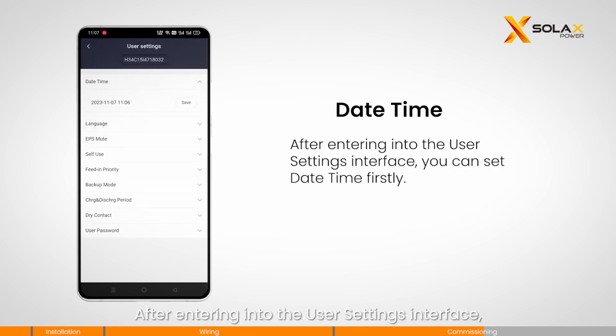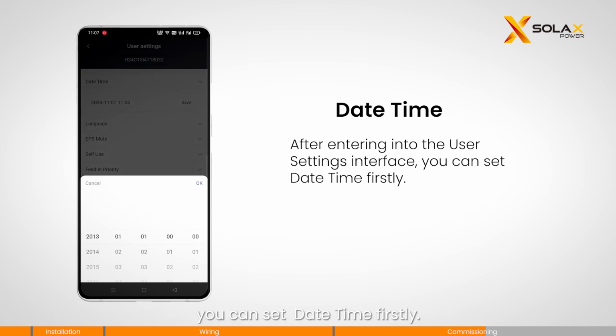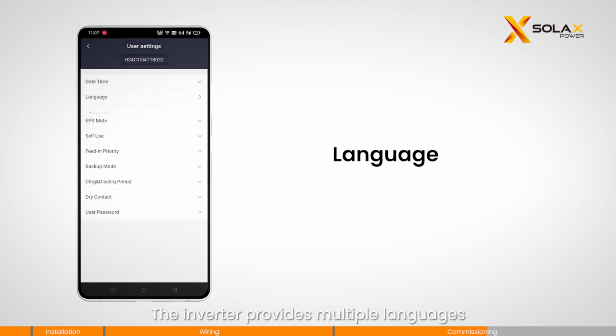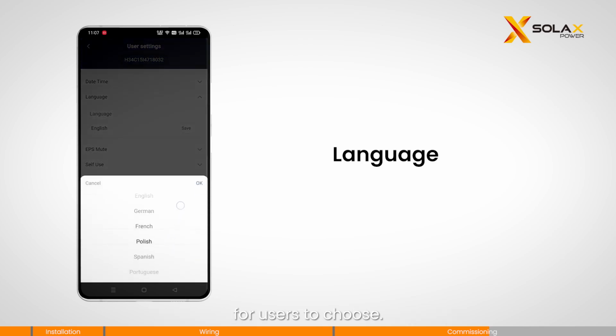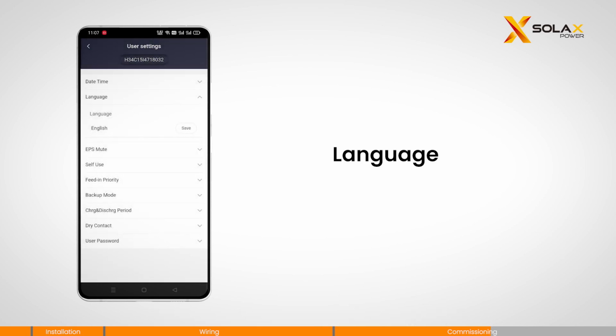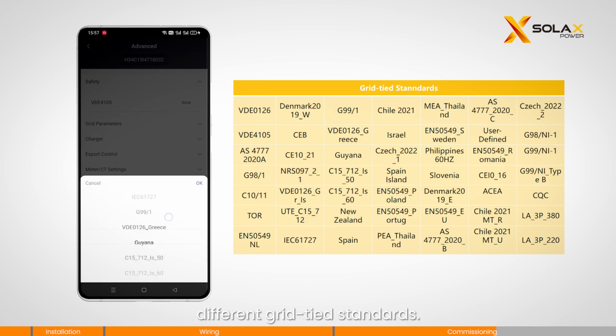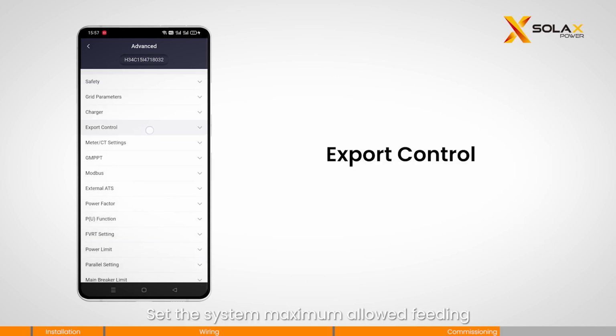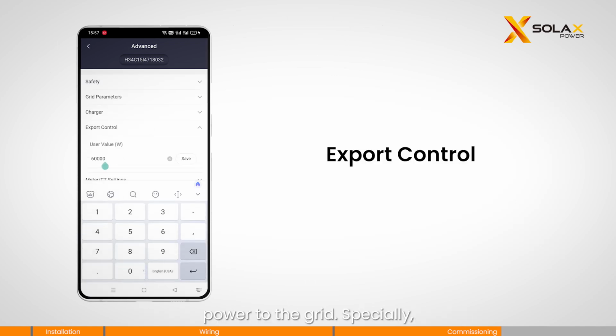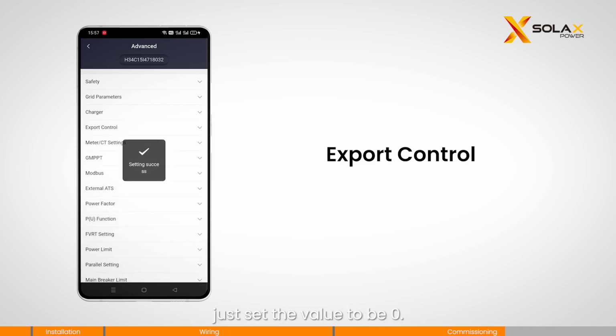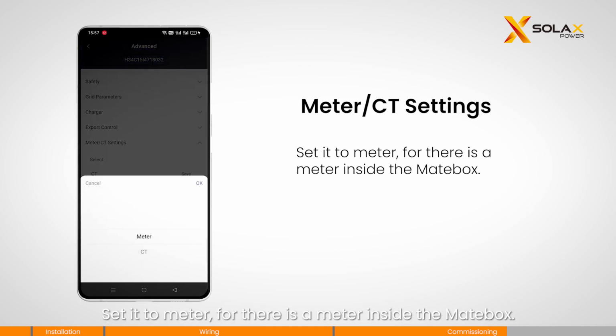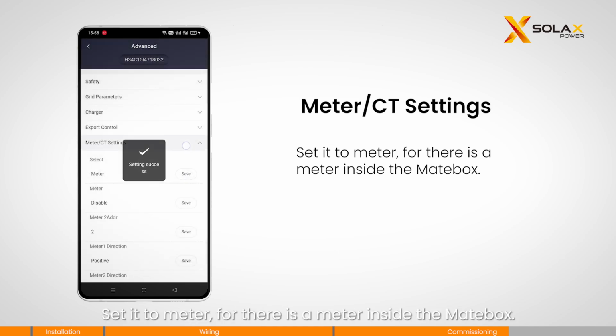After entering into the User Settings interface, you can set date and time firstly. The inverter provides multiple languages for users to choose. Here you can set the safety code according to different grid-tied standards. Please refer to the table for some main codes. Set the system maximum allowed feeding power to the grid. Especially, when there is a zero injection requirement, just set the value to be 0. By default, the inverter is set to CT, set it to meter, for there is a meter inside the Matebox.